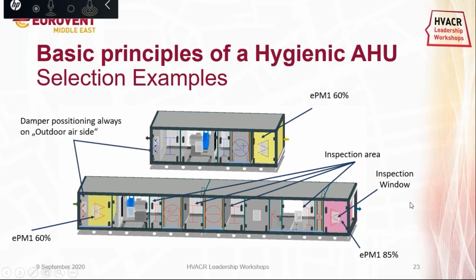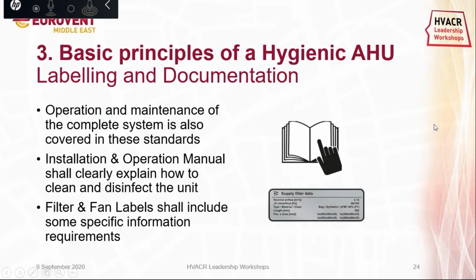Damper positioning is at the outdoor air side as required, as you can see here. Drip trays are also positioned as required in the norms, one at the outdoor intake air section, and below the cooling coil and runaround coils. Labeling and documentation. Yeah, it's not only the design and construction of the unit, but the operation and maintenance of the complete system is also covered in these standards. For example, the IOM shall clearly explain how to clean and disinfect the unit. Also, the filter and fan labels shall include some more specific information compared to what's required in standard air handling units.